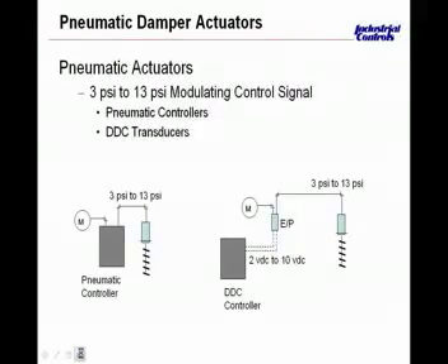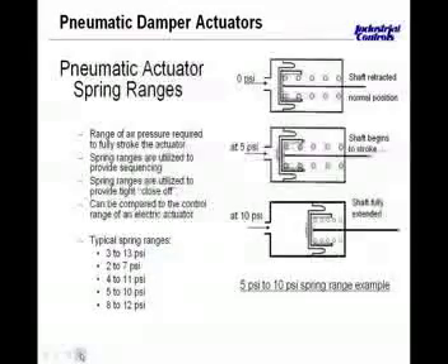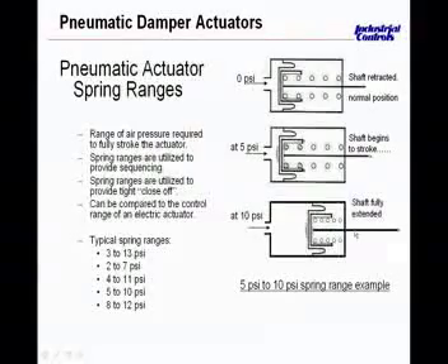Okay, we'll advance to the next slide. Here we're talking a little bit about spring ranges again, and in this example we've got a 5 to 10 pound span spring, and as we touched on before, at 0 pounds the actuator stem is fully retracted. The spring, of course, is what's doing that. At 5 pounds or thereabouts, we'll begin to extend the actuator shaft to the point where at 10 pounds we'll be fully extended. Now, of course, there's going to be some opposing force on that actuator stem, and if that opposing force is greater than 10 pounds, that 10-pound pressure might have to rise to 10 or 12 before that actuator is fully extended.